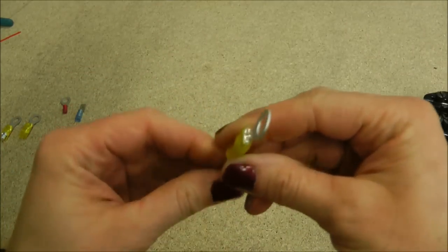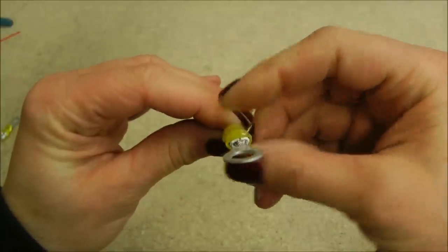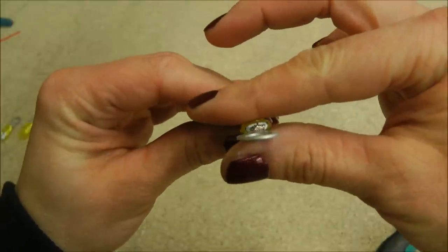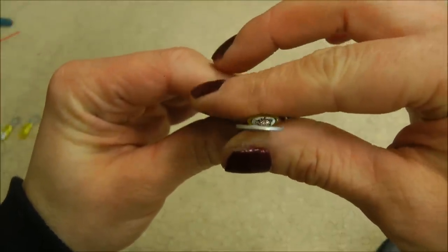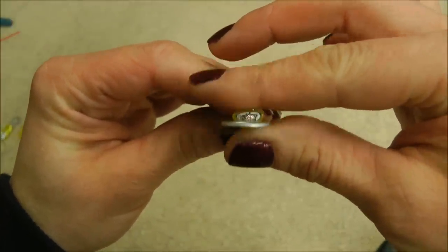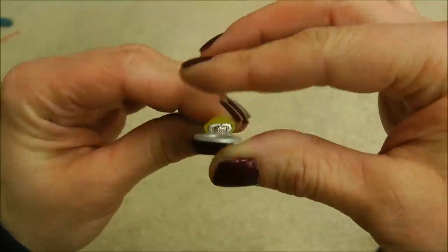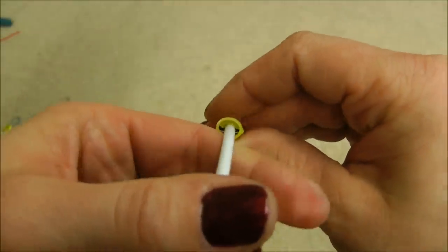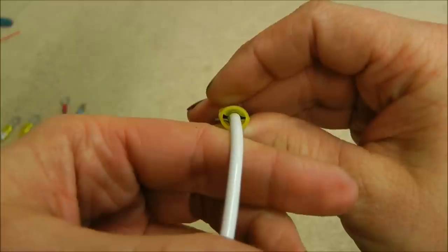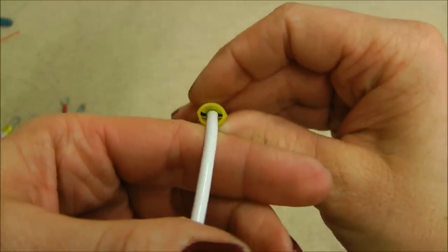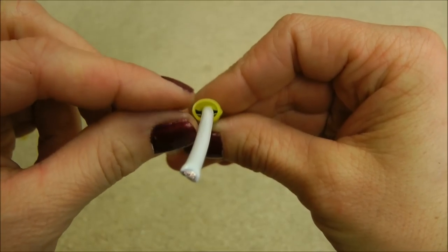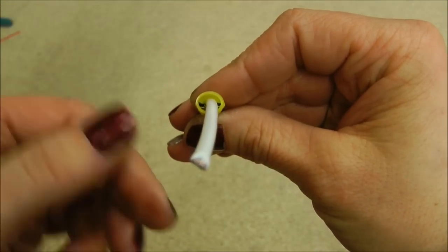Alright, what we have, what would have been the back side with the smooth curve, you'll see it crushes the barrel around the wire evenly. The other side you'll see that it has encased the insulation but not gouged into it, it hasn't crushed it, and then it pinches on either side of it.